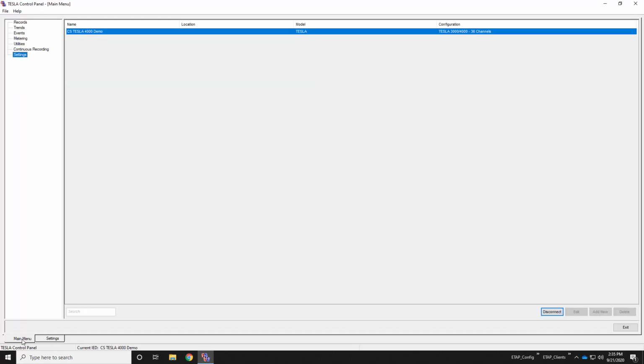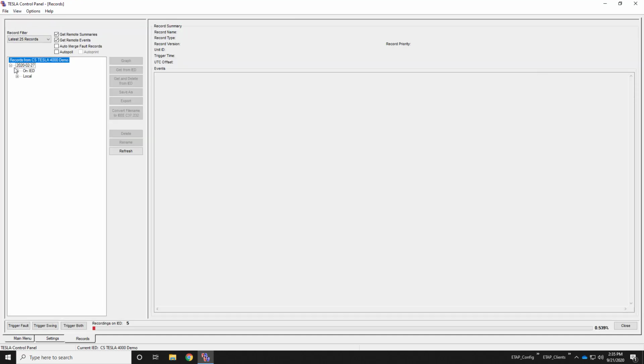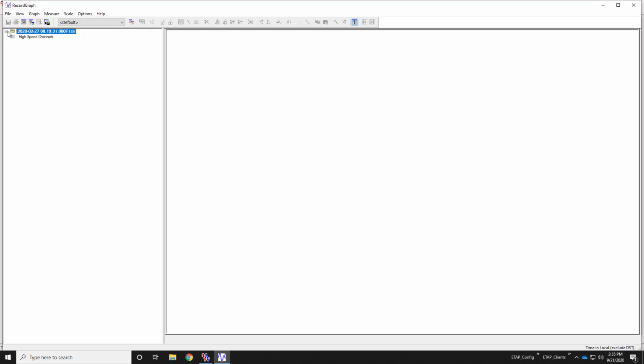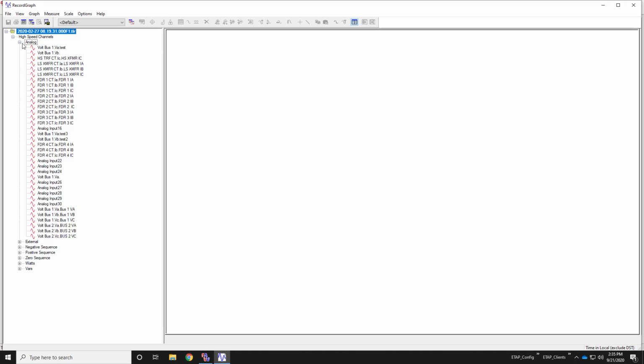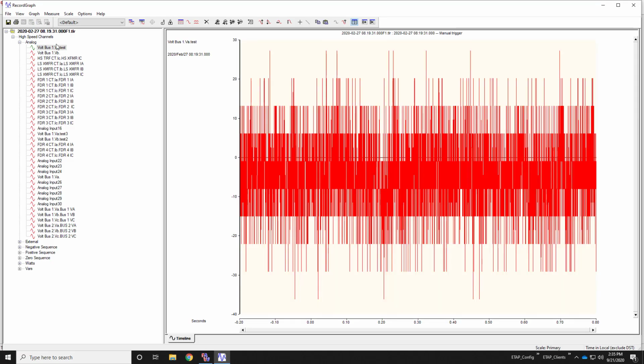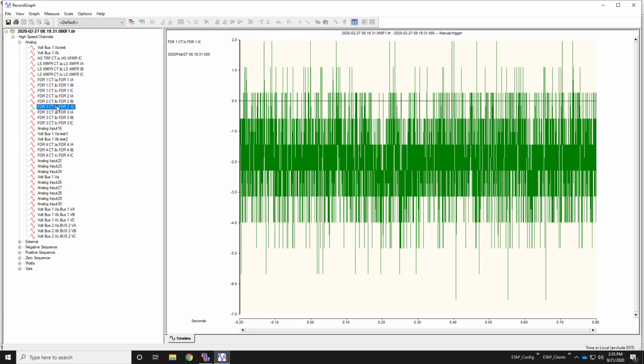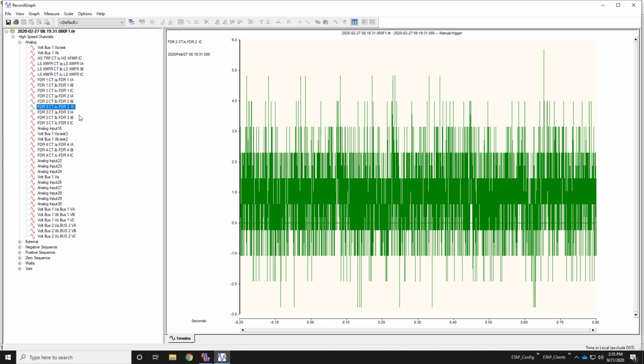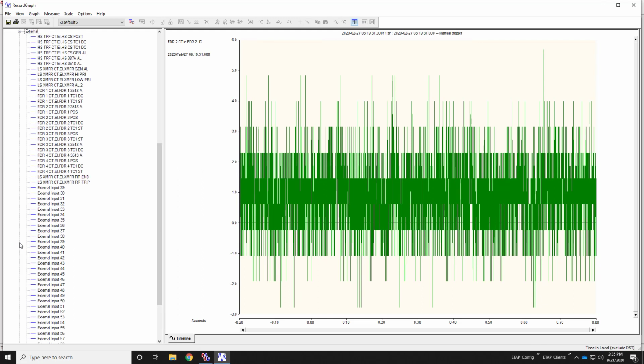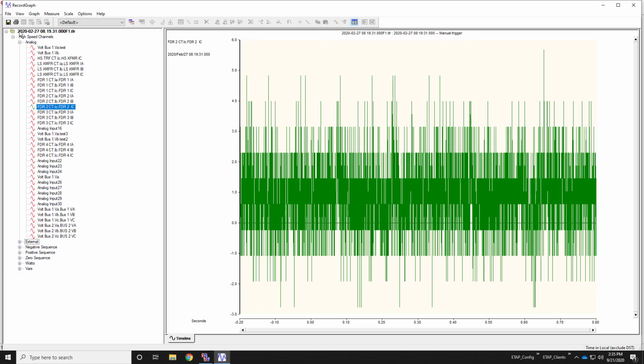Here I can look at the various data. I can look at my records. I'm going to go to an existing fault on the device and open the record graph. Here is my analog measure data. I can go through different measurements and see the measured data during this ComTrade, during this fault. Here I can look at external data, so the inputs and outputs and the circuit breaker positions. Additionally, I can look at my calculated data, so my negative sequence, for instance, of my voltage.